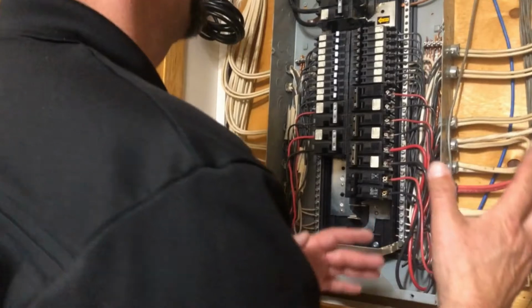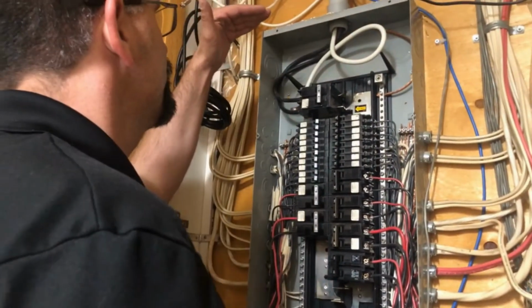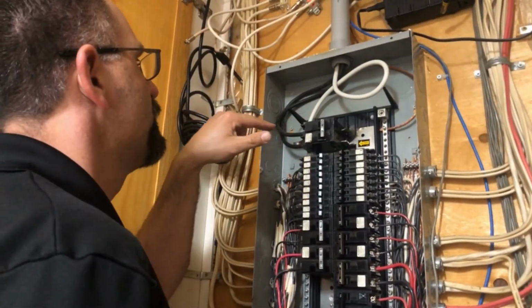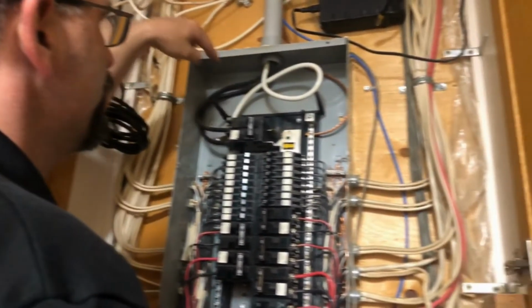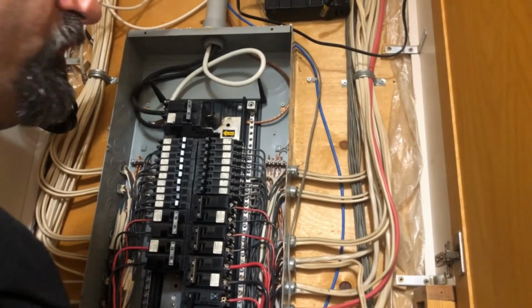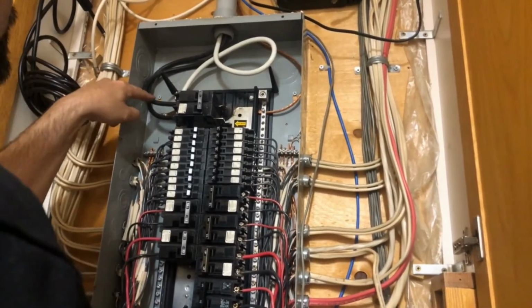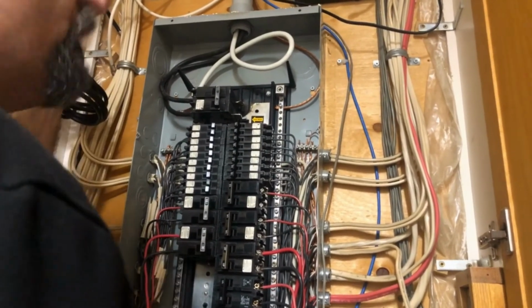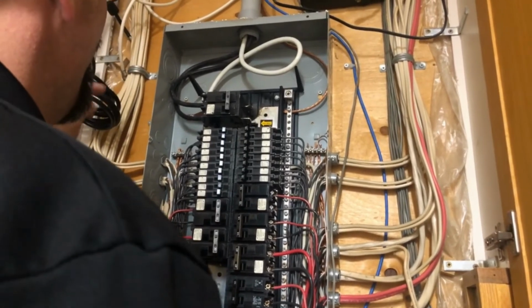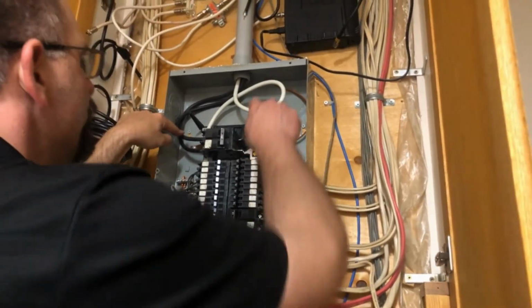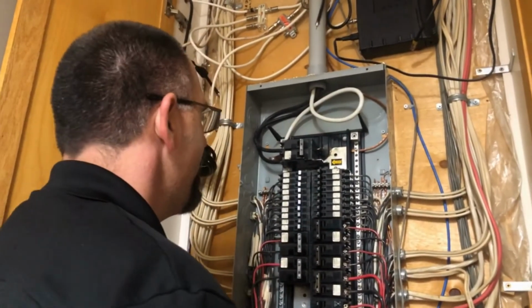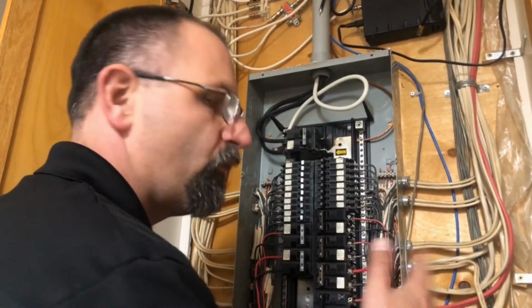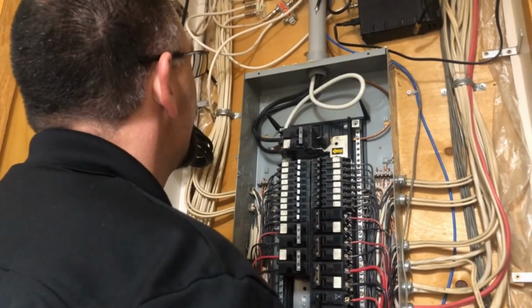So we've got two parts to the electrical panel. The upper section is called the service side. There's our main 100 amp breaker. These conductors that are coming in here, we've got basically two hots and a neutral. These two hots give you your 240 volts, and between this hot and your neutral wire gives you your 120 volts. And that is distributed through the panel for all the different loads that you have in your home.